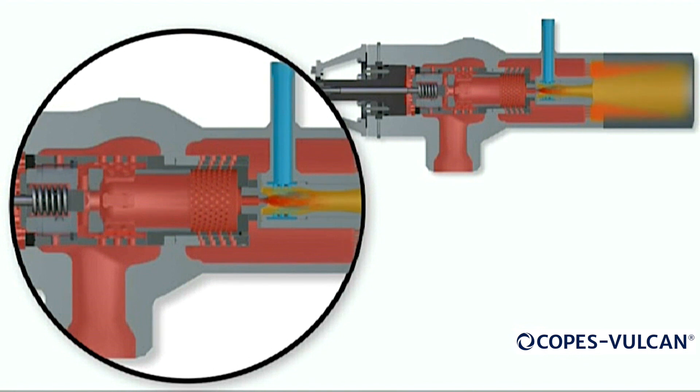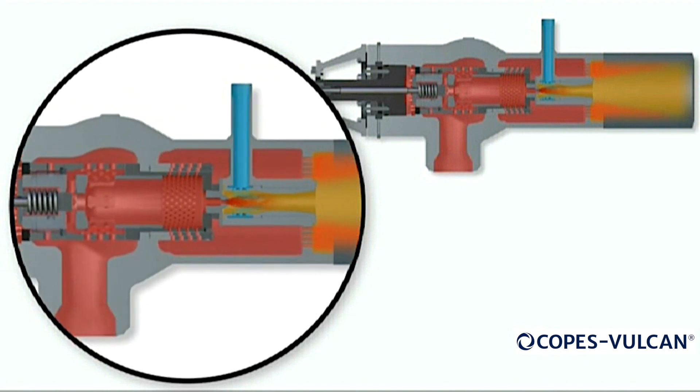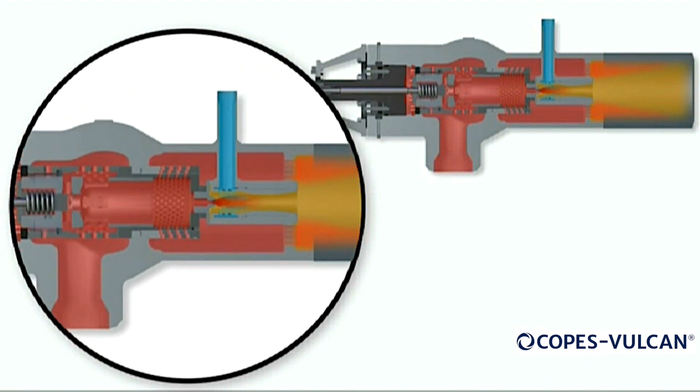After the inlet steam has passed through the distribution spacer, it now travels through the main seat area to the underside of the main plug via large feed ports. With the main plug now lifted, the pressure-reducing ports of the cage are now open to allow the steam to be pressure reduced in a controlled manner.